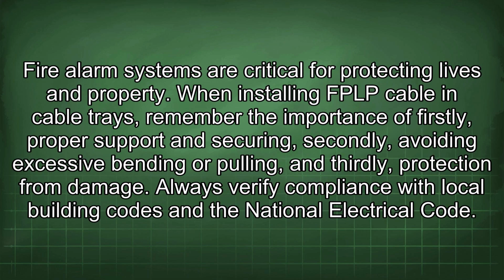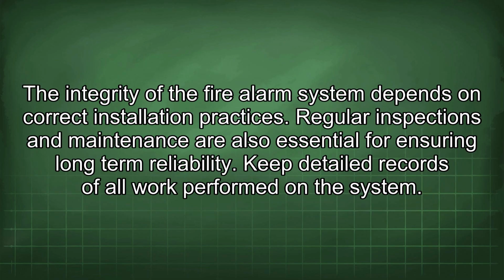Fire alarm systems are critical for protecting lives and property. When installing FPLP cable in cable trays, remember the importance of firstly, proper support and securing, secondly, avoiding excessive bending or pulling, and thirdly, protection from damage. Always verify compliance with local building codes and the National Electrical Code. The integrity of the fire alarm system depends on correct installation practices.